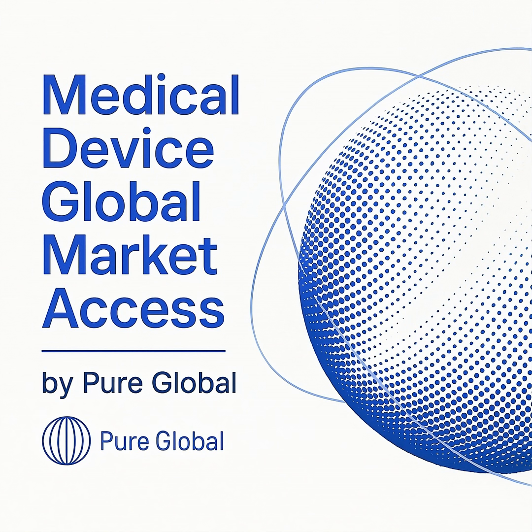Class 1 devices are low risk and subject to the least regulation. Examples include adhesive bandages and manual stethoscopes. Class 2 devices pose a moderate risk and make up the largest category of devices. They often require a pre-market notification, or 510(k), submission to demonstrate they are substantially equivalent to a legally marketed device. Examples include powered wheelchairs and syringes.